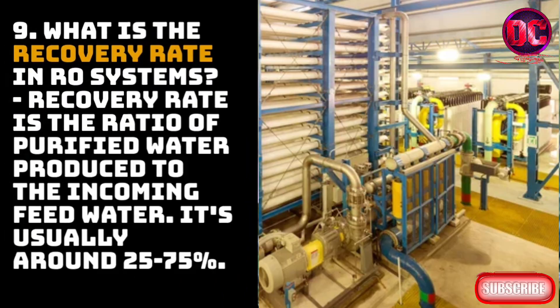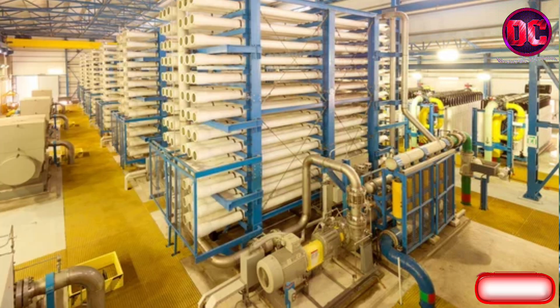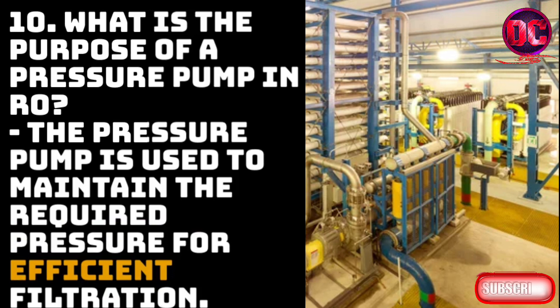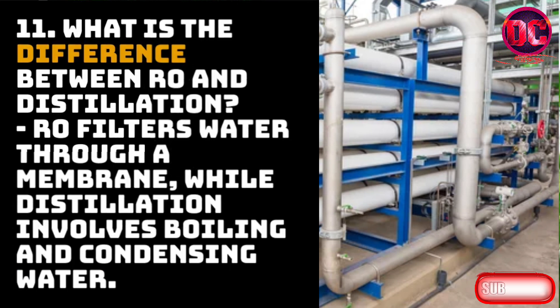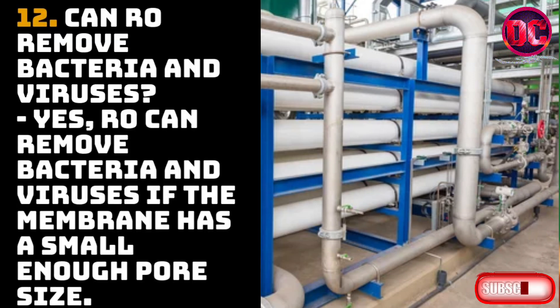9. What is the recovery rate in RO systems? Recovery rate is the ratio of purified water produced to the incoming feed water — usually around 25 to 75%. 10. What is the purpose of a pressure pump in RO? The pressure pump is used to maintain the required pressure for efficient filtration. 11. What is the difference between RO and distillation? RO filters water through a membrane, while distillation involves boiling and condensing water. 12. Can RO remove bacteria and viruses? Yes, RO can remove bacteria and viruses if the membrane has a small enough pore size.